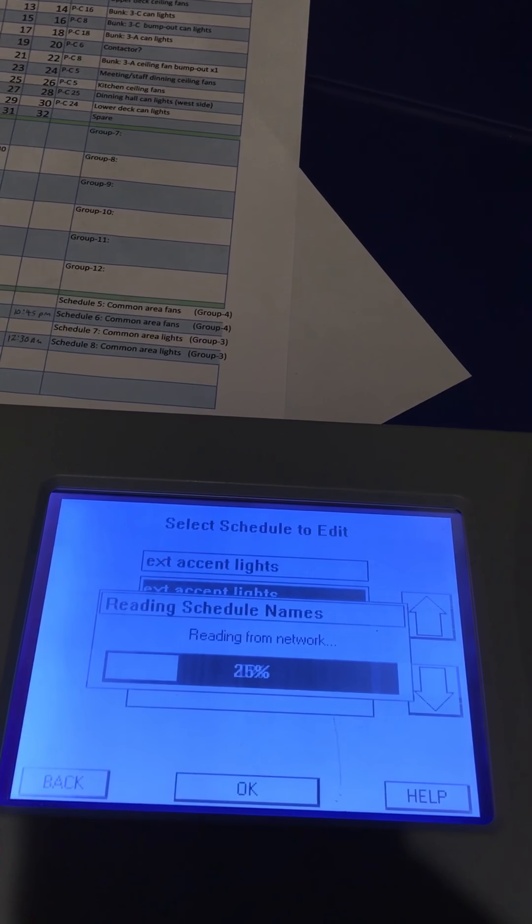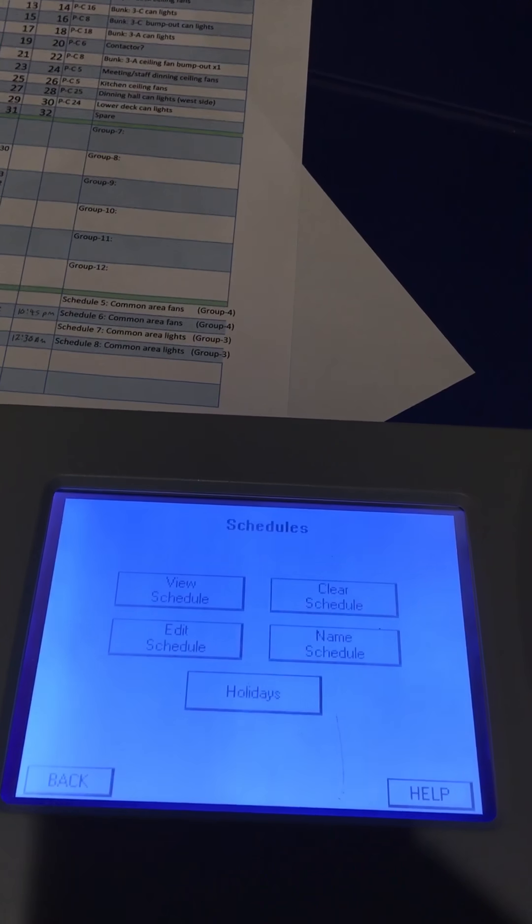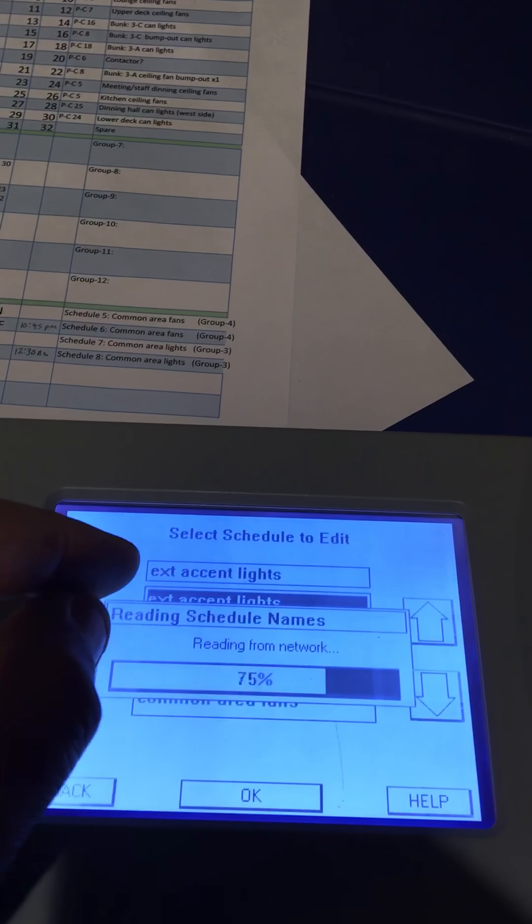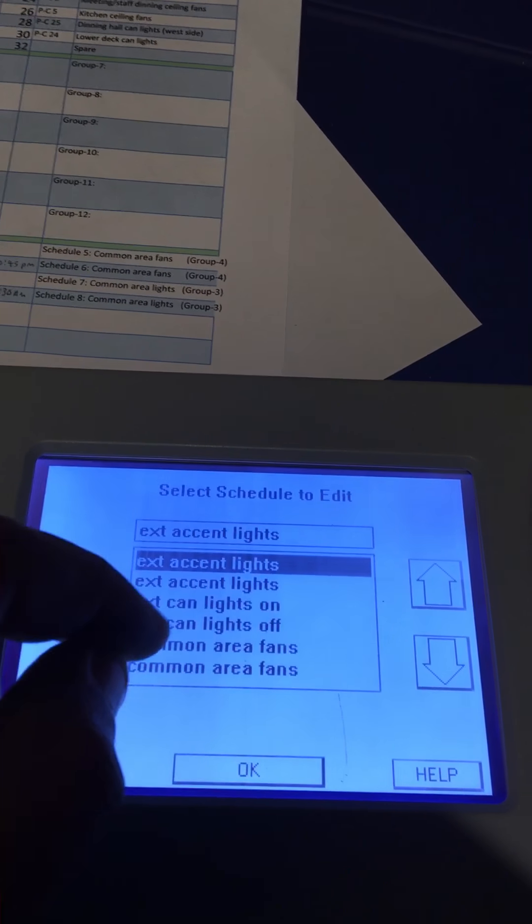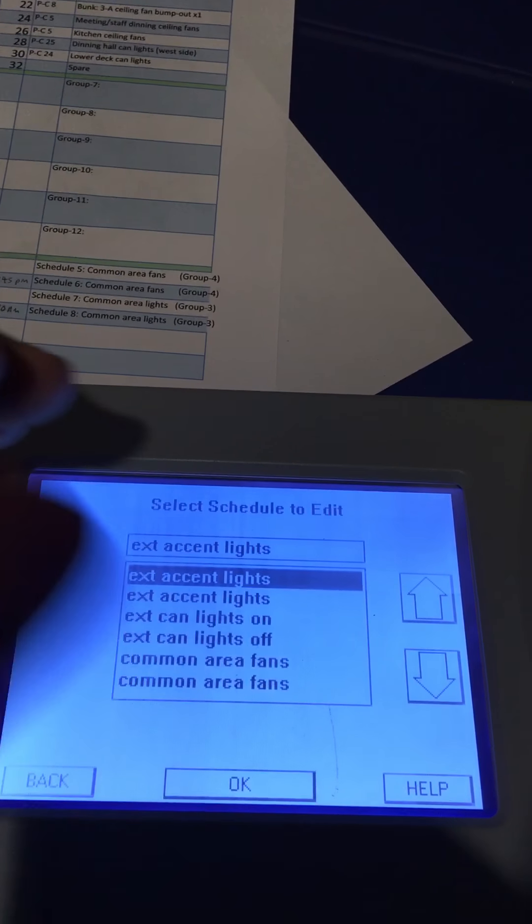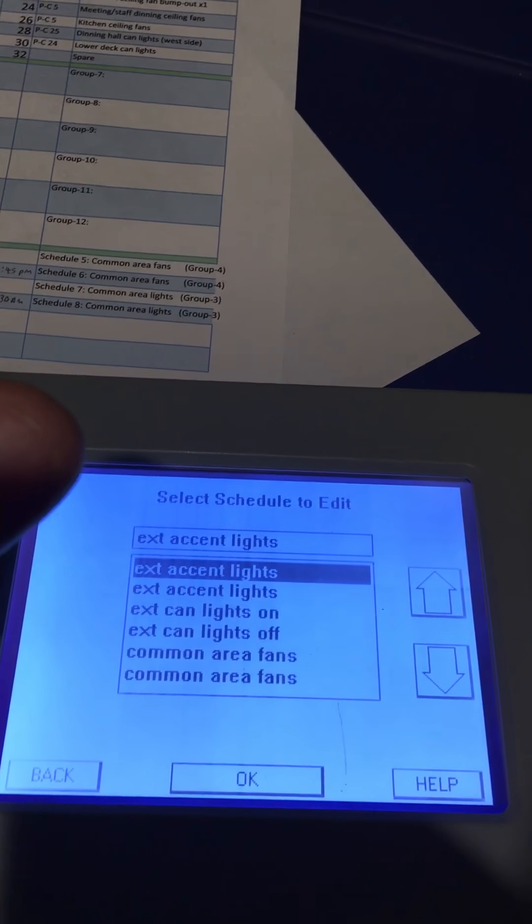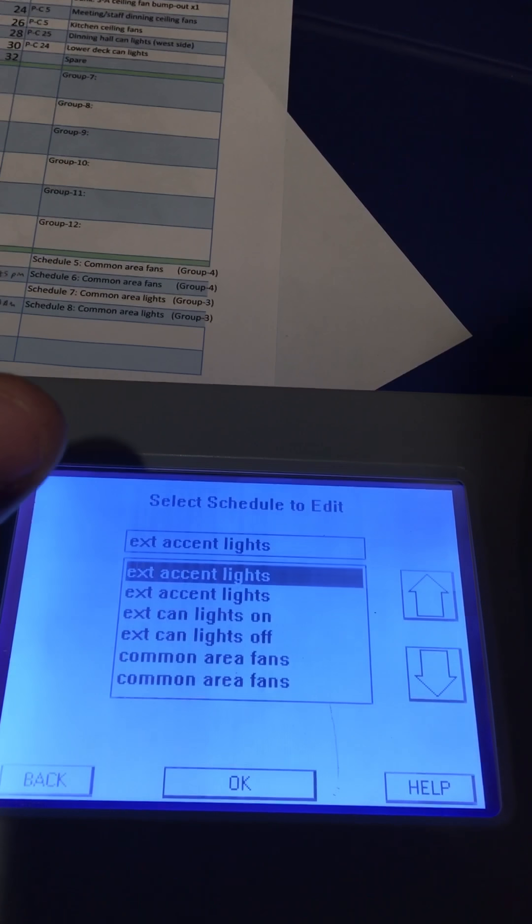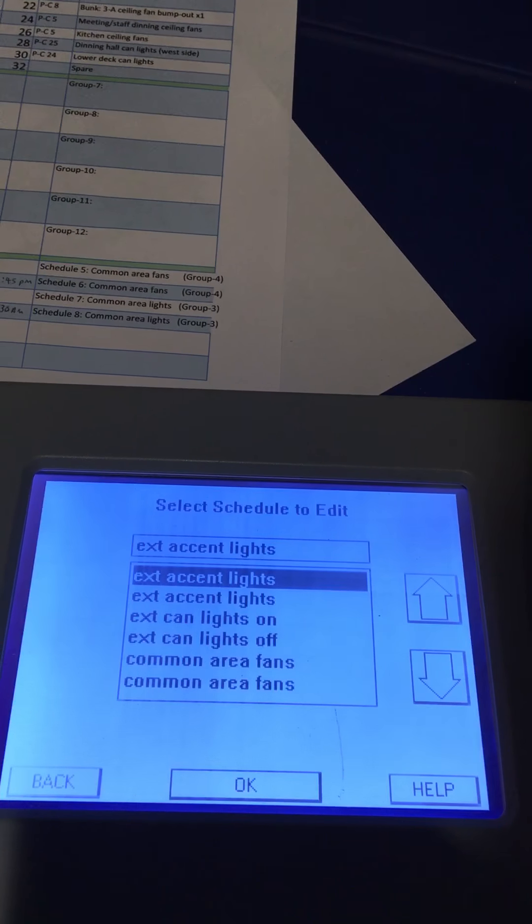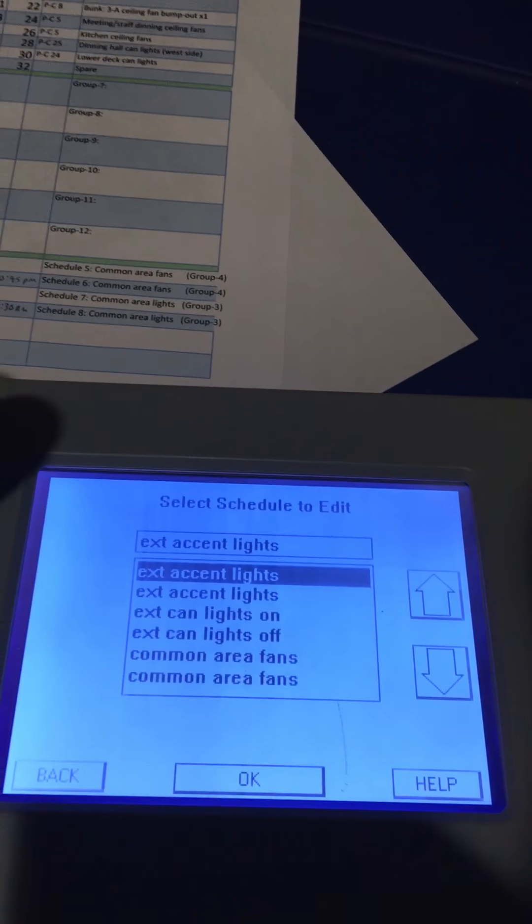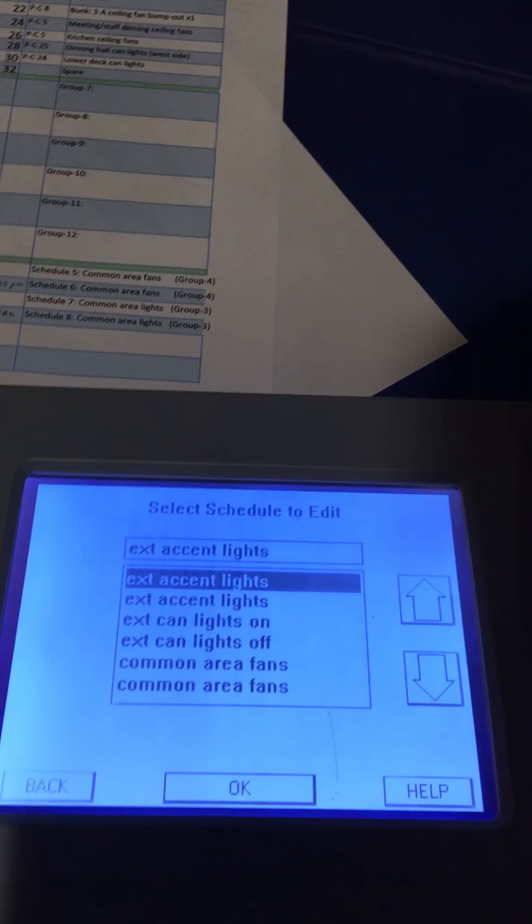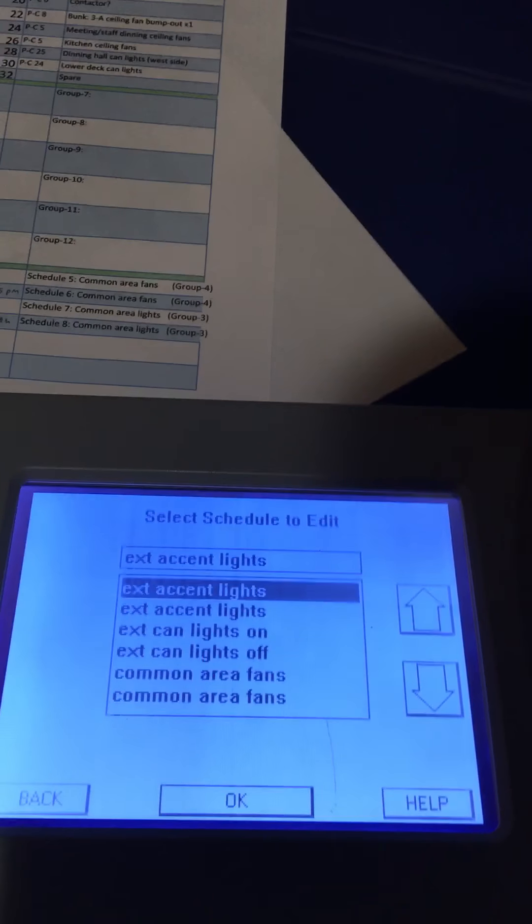Back to edit schedule. What we can do is go down and find schedule number 11. Schedule number 11 would be the exact same schedule name and everything, but we would just do a group off as opposed to group on. Schedule 10 turns group 7 on at 12:58, and schedule 11 would turn that group off at 4 AM or whatever time.